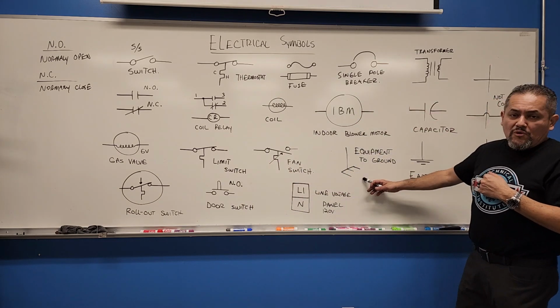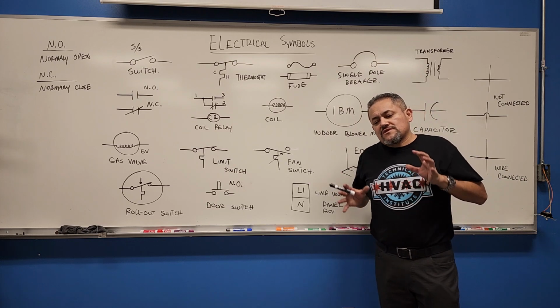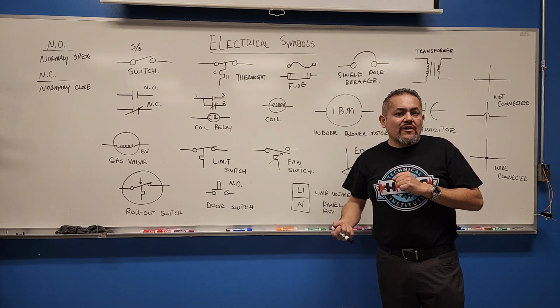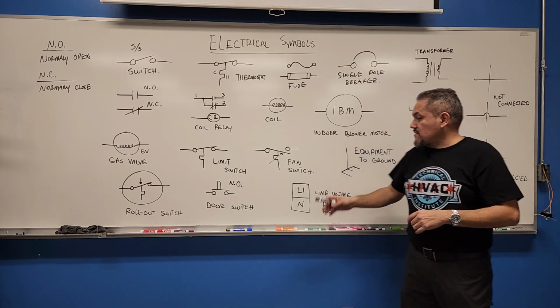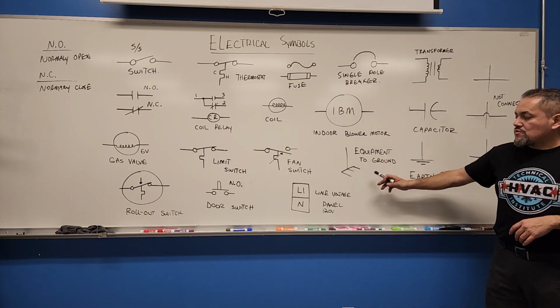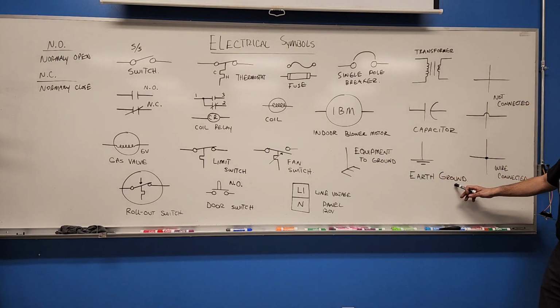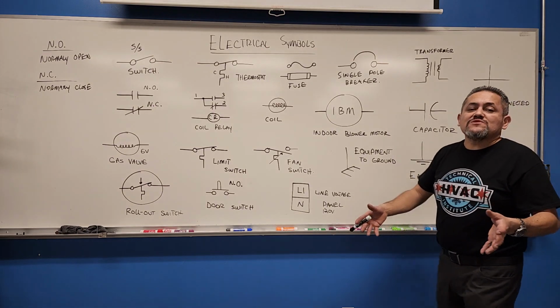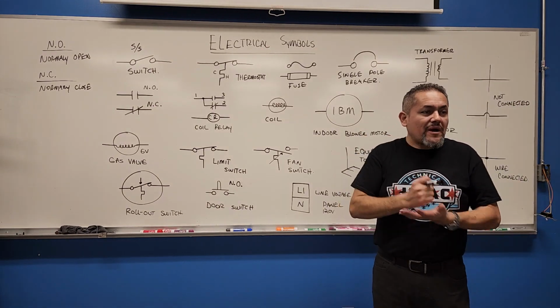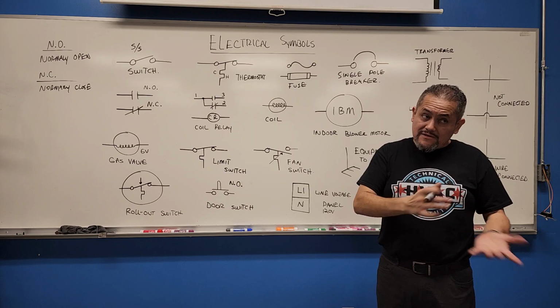Equipment to ground, very important. Any electrical component that goes inside the furnace has to be connected to the ground of the whole furnace. That's what it means, electrical equipment to ground. Earth ground, this is the furnace. The whole furnace has to be connected to the earth ground. It has to be somehow touching earth ground, so that's the difference.